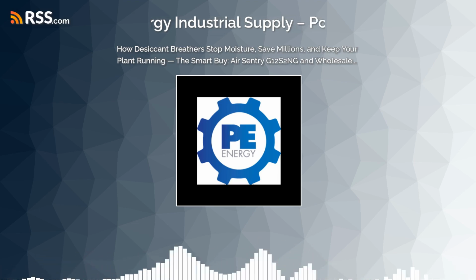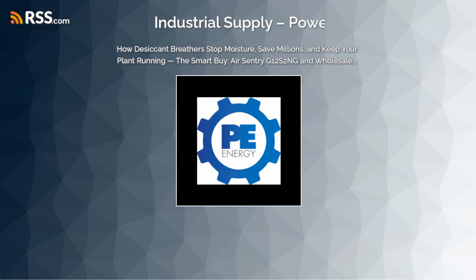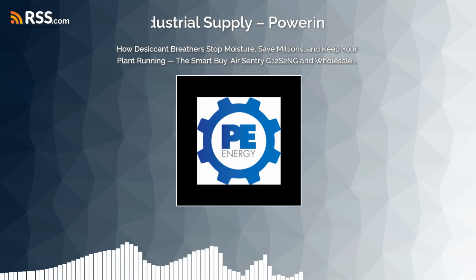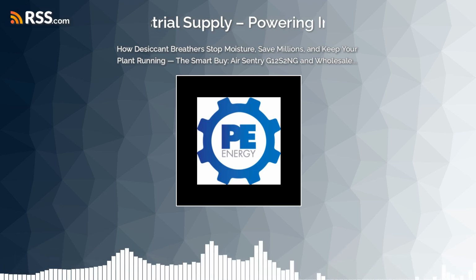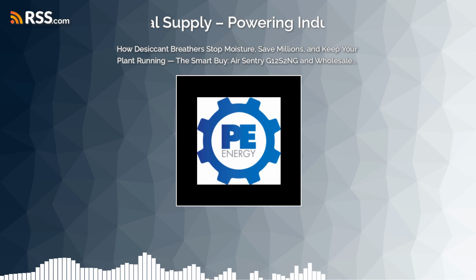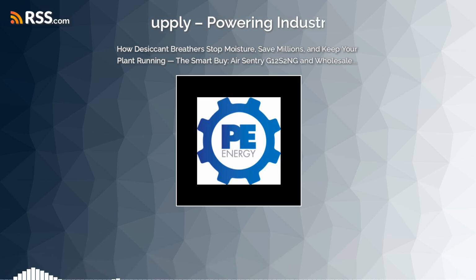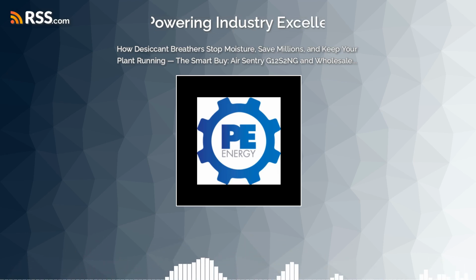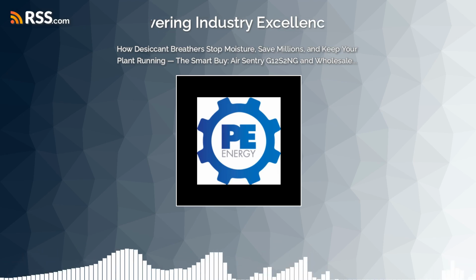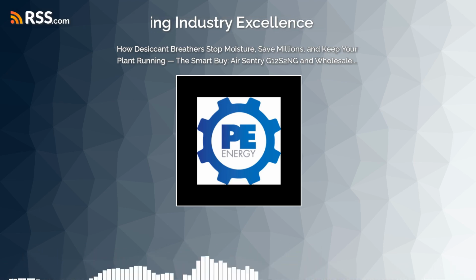Okay, that makes sense, it's pushing air out. The exhale is harmless. The danger is the inhale. The shift ends or the load drops and that massive tank starts to cool down. The air inside contracts, the oil volume shrinks, and now you have a vacuum. And nature hates a vacuum, so that tank just sucks in air from the outside to equalize the pressure.